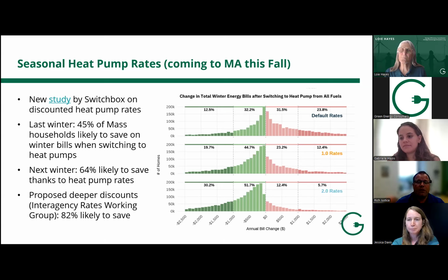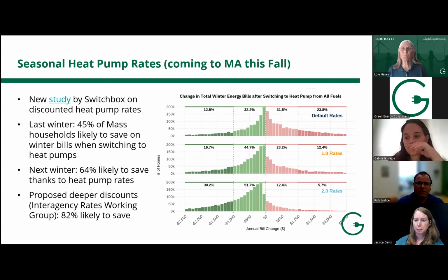Go ahead, Rich. So heat pump water heaters, going back to Loie's slide, are something you have to think about. They are very efficient and will do great if you put them in the right setting. The trick is they typically need 700 to 1,000 cubic feet of air around them to provide enough airflow, and they're almost 6 feet tall, so you need space around them depending on where you're trying to put them. Also, a standard heat pump water heater removes heat from the air, so you don't want to put it in a living space. I believe this question, mentioning it's not in the basement, indicates it's somewhat of a heated living space, and you don't want to make that area colder.